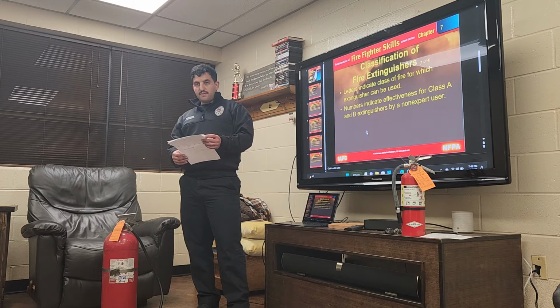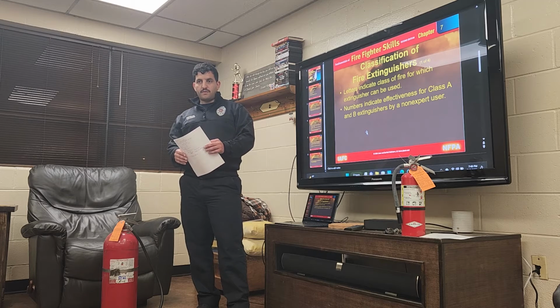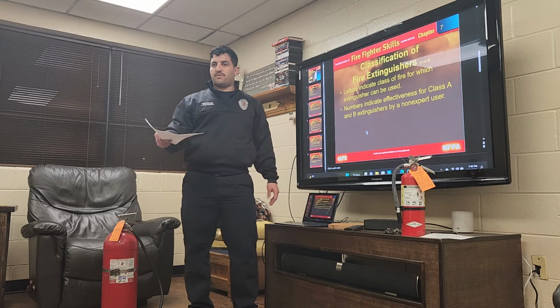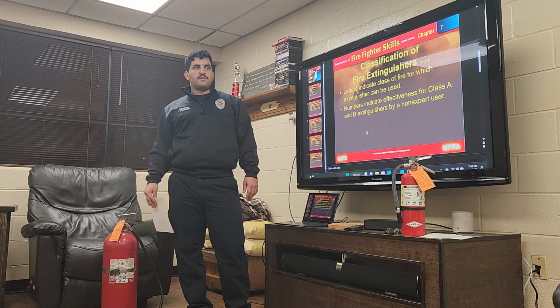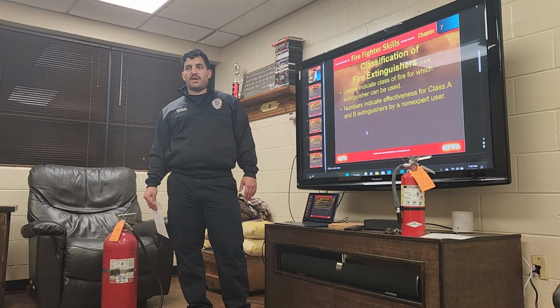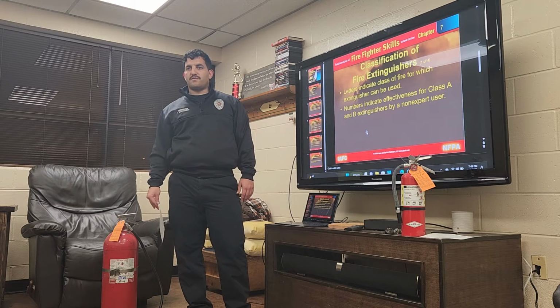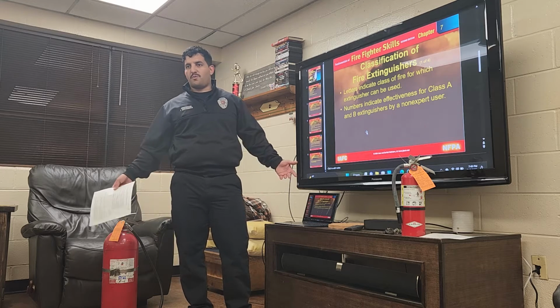So a 5 pound Class A extinguisher would say 5A on it? No. Each number is 1.25. So if it's 5A, it would be 6.25. It would be 1.25 times 5.